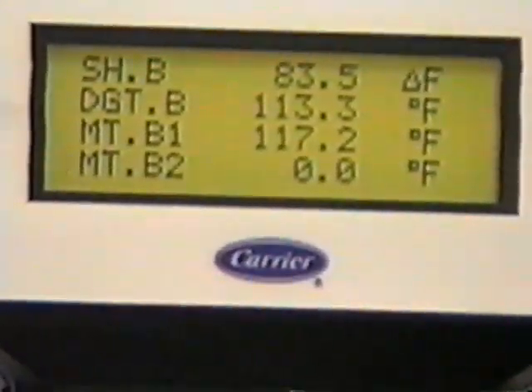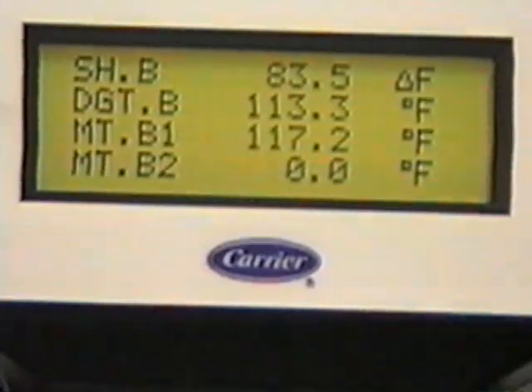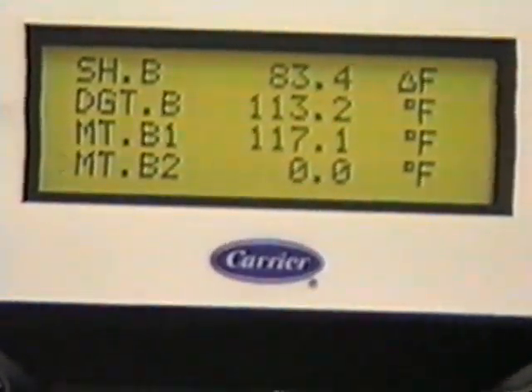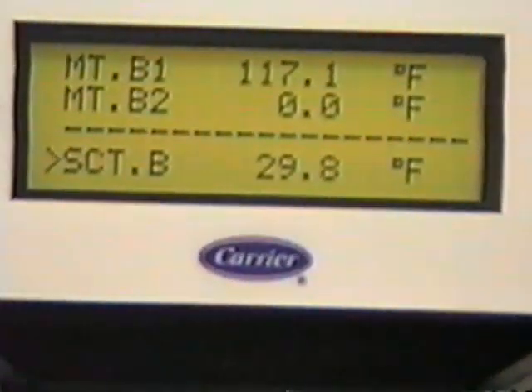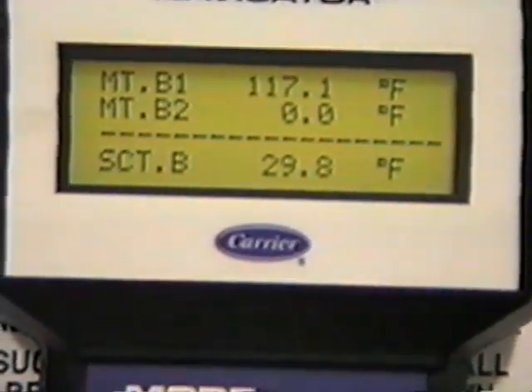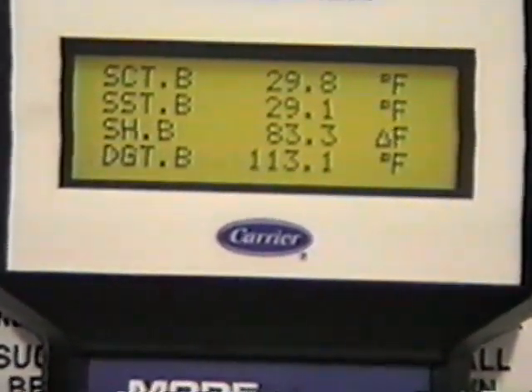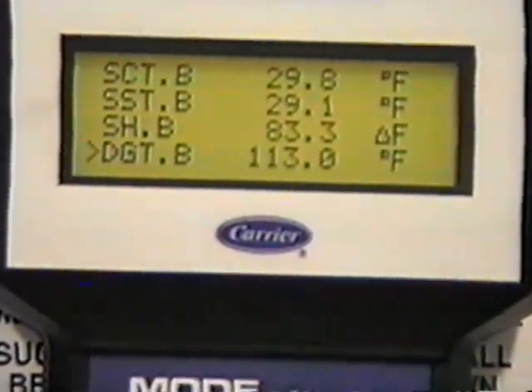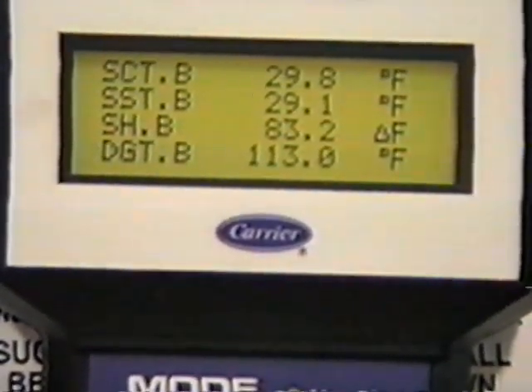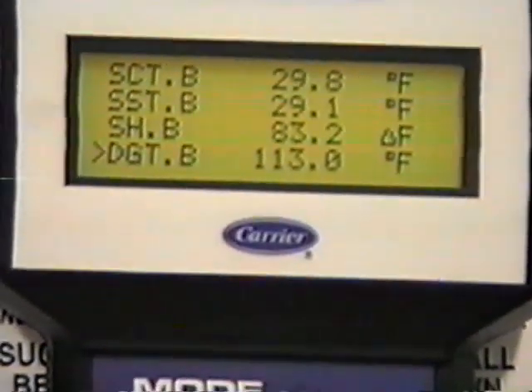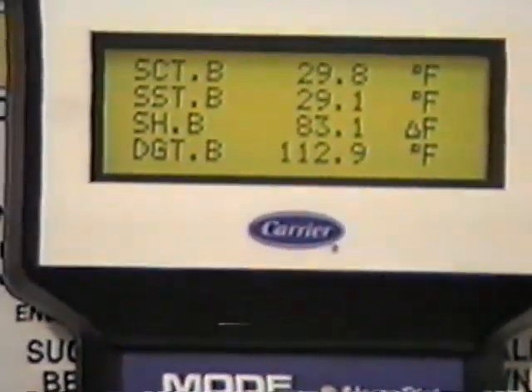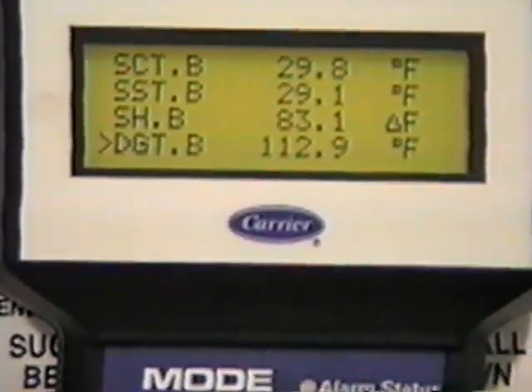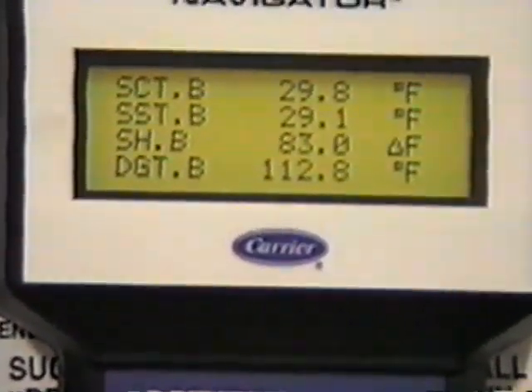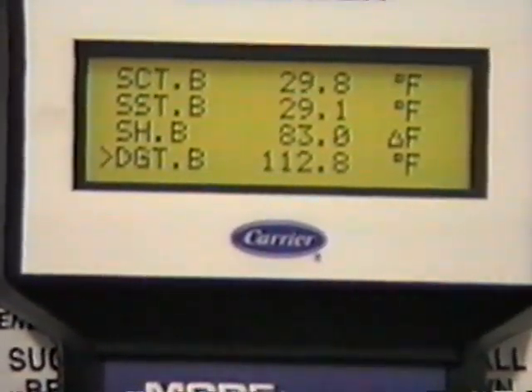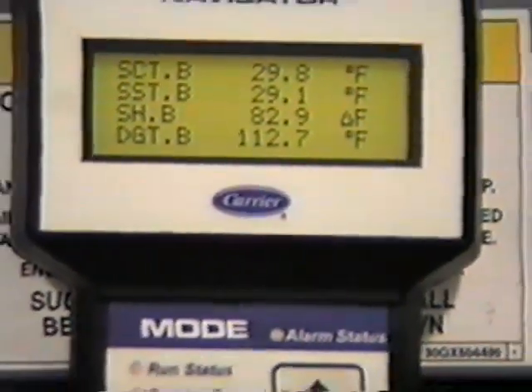Okay, so there's about, I don't know, 7 or 8 items on that list. It'll allow you to see only 4 on the screen at a time, so keep in mind there's probably more there if you don't see exactly what you're looking for. So you're gonna have two different sets of discharge pressure, A and B? Right. There are certain temperatures, again, unique to just the chiller, or to the common chiller. And then there are certain temperatures unique to each individual circuit. So it'll identify that. And again, the menu.